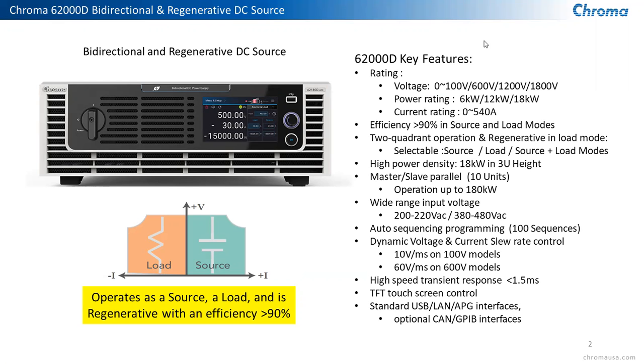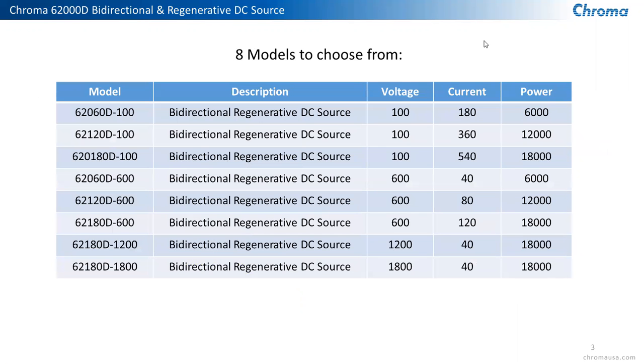Has a great touch screen front panel, makes it very easy to operate the unit, very minimal buttons on the front. Standard comes with a USB interface, Ethernet, LAN interface. Also has analog control. And with the analog control, we get down to a latency, or the time it takes to control the unit from the analog input to the output, in under 600 microseconds. So the unit, as I mentioned, is very compact. The product, they've done a great job with packaging and creating a nice operation of this unit from the front panel. 8 models that I mentioned, 100 volt, 600 volt, 1200 volt, 1800 volt, from 6 kilowatts to 18 kilowatts, currents ranging from 40 amps all the way up to 540 amps. So we have enough units to cover a wide variety of different applications for you.